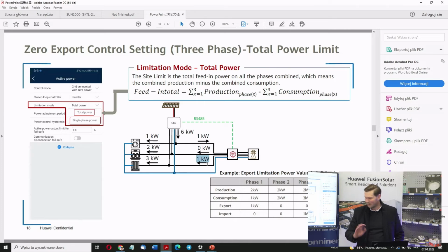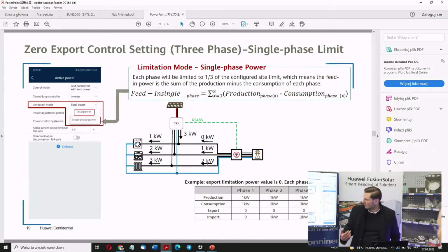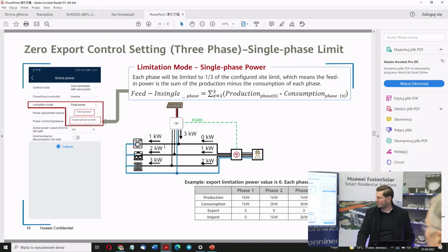For you, probably the most common scenario will be this one — the single phase limit. You don't allow the inverter to export anything to the grid. But the problem is that even though there's demand, the inverter will always limit the power to the least loaded phase — in our case, 1 kilowatt here, 1 kilowatt on the second phase, and 1 kilowatt on the third phase. So what's missing, we need to import from the grid.